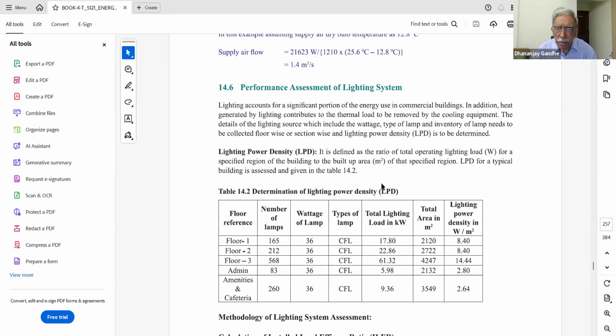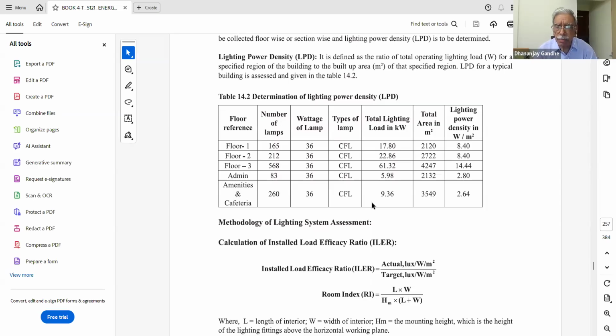When the lighting system is designed, of course, they take into consideration that all lamps will be operating and the total built-up area figure is known to calculate lighting power density, and that's how the design will be done. But in actual practice, all lamps may not be working, so you have to know the total lighting existing at a particular point of time. First, let us see how the calculation of lighting power density is done. For an existing building, not at the design stage, we have to assess the lighting power density and whether it conforms with the design figure. That is what we assess first as the performance assessment.